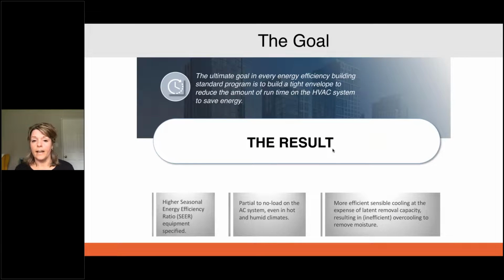The ultimate goal in every energy efficiency building standard program is to build a tight envelope in order to reduce the amount of runtime on our HVAC systems and save energy. That's the goal. But the result is we're typically using far more energy efficient HVAC equipment to meet certain building standards, with a really high SEER, which reduces our moisture removal. We're now in more partial to no-load AC system conditions, even in hot, humid climates, so we're not running the AC as much, which is the goal.